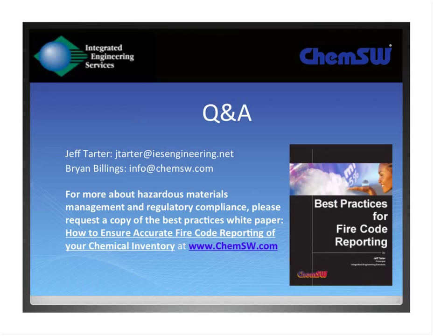Q&A: The first question for Jeff: Do corridors serving control areas require separation as well? No. Corridors are not required to be separated from the control areas they serve. Under the current code, corridors aren't required to be fire-rated at all in a sprinkler building. So you could have a multi-control area building with four control areas but no rated fire or egress separation system.